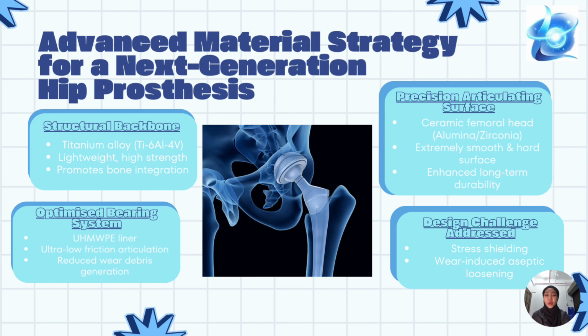The structural backbone of the implant is formed using a titanium alloy, titanium 6 aluminium 4 vanadium, which offers a high strength to weight ratio while promoting bone integration and reducing the risk of implant loosening. An optimized ultra-high molecular weight polyethylene liner is incorporated as the bearing system to provide ultra-low friction articulation and minimize wear debris generation. In addition, a precision ceramic femoral head made from alumina or zirconia is selected due to its extremely smooth and hard surface, which enhances long-term wear performance.